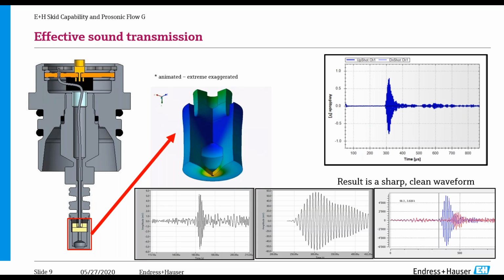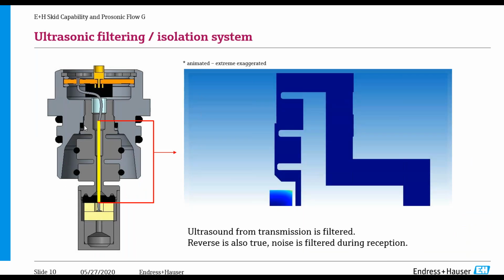What you don't want is what we see here, which you can see at the bottom left that just popped up in the graphic. We have a lot of noise. So you have a lot of noise in the background. It's hard to tell the true signal versus the noise. The other one is you really don't get a strong peak. And when you're doing this time differential, it's hard to find exactly what measurement value we want to take from that type of elongated signal. So that's on our transmission.